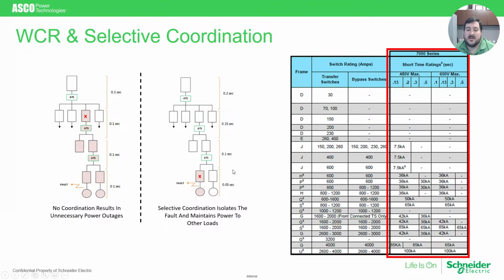So that means that ATS can be applied in applications further and further up the chain, where your fault current may be higher the closer you are to the source, and where your withstand duration, because the circuit breakers are coordinated to trip slower the further up you go, the ATS is coordinated to go with that breaker. So down here, this ATS only has to withstand a fault for 0.1 seconds, while one up here must withstand a fault of 0.15 seconds, and so on and so forth.